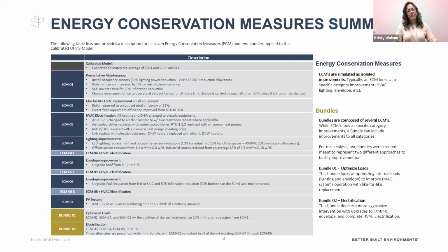So we looked at a variety of ECMs. It's hard to see here, but we evaluated each one. ECM 1 is preventative maintenance, because deferred maintenance tends to be the rule, not the exception—so get your building to a baseline first with that. But we also looked at a like-for-like HVAC replacement, and at electrifying the heating equipment with heat pumps. Then we bundled them: the first bundle is like-for-like with optimized loads, and the second bundle is electrifying your heating system with those optimized loads.